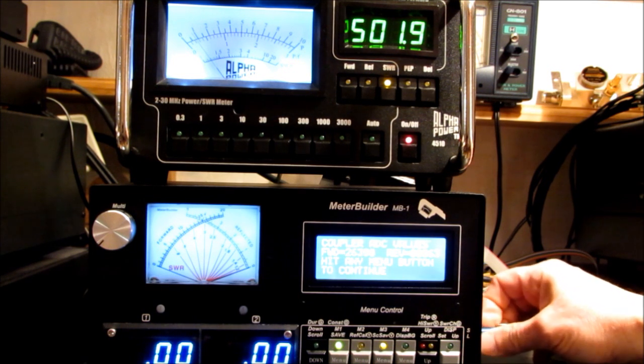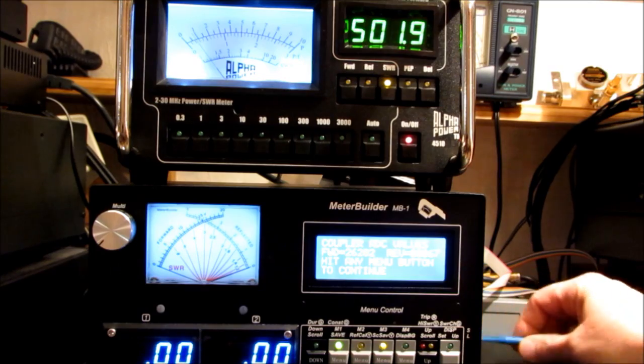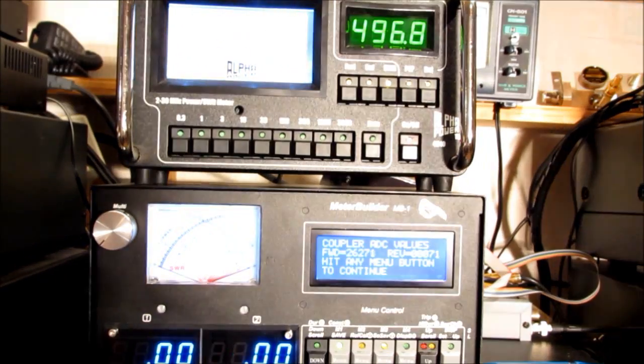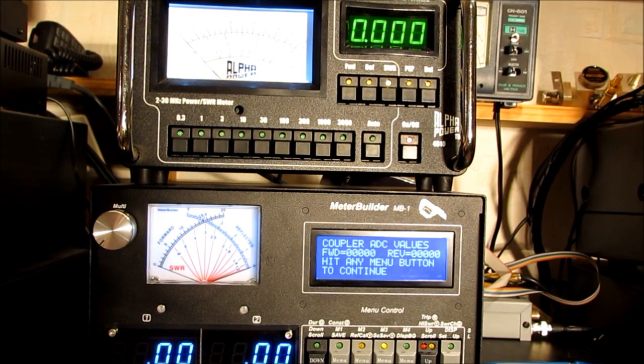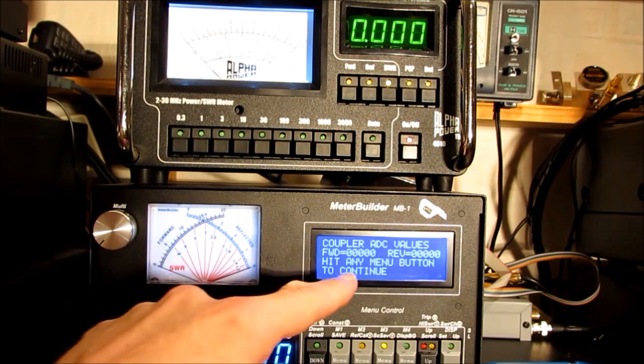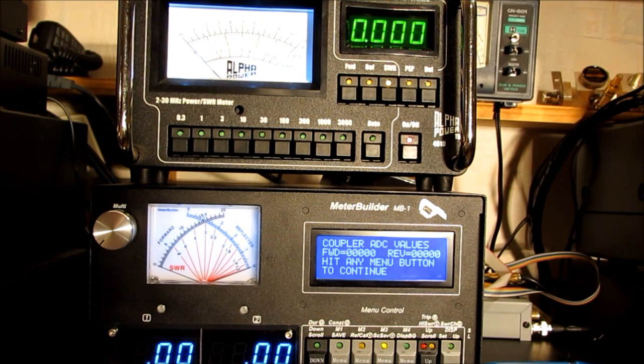Okay, this is a case where I am actually at the max value, and the maximum output that this coupler was capable of creating, in terms of voltage, was approximately 26,000. Not too bad, we can still get pretty good resolution with that, but you may find if the coupler you're working with doesn't put out approximately 6.14 volts at full scale, you won't be able to drive this number all the way to 30,000 as we were trying to set it. It just means the coupler you're dealing with has somewhat low sensitivity, but this coupler is certainly usable with MB-1. So in effect, we have the forward coupler pot adjusted, and we can continue.